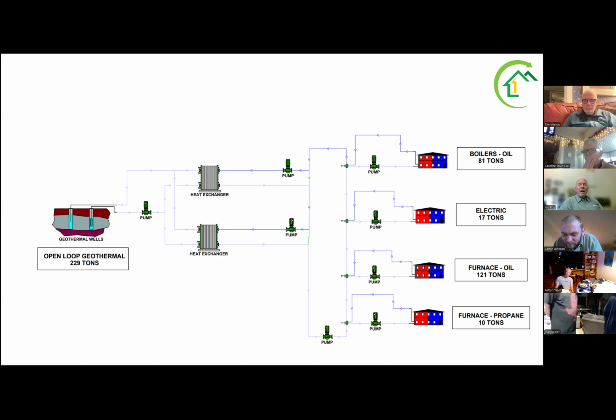But I would be hesitant to figure anything above the COP of the actual heat pumps plus the energy consumption of the circulators on the system, which is going to be in the neighborhood. Just the heat pumps alone is normally in the neighborhood of 4 COP, so we degrade that to 3, for a completely all heating system snapshot. That would be a safe number to figure.